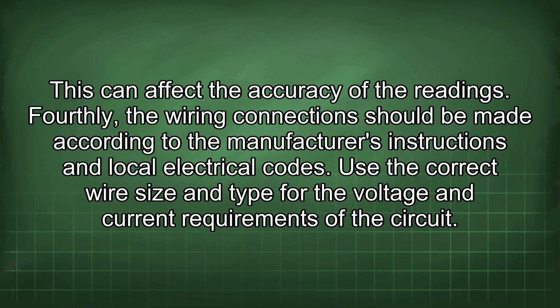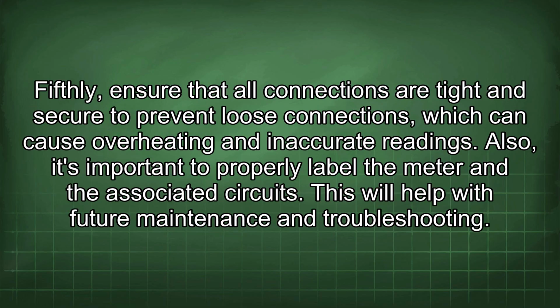Fourthly, the wiring connections should be made according to the manufacturer's instructions and local electrical codes. Use the correct wire size and type for the voltage and current requirements of the circuit. Fifthly, ensure that all connections are tight and secure to prevent loose connections, which can cause overheating and inaccurate readings.